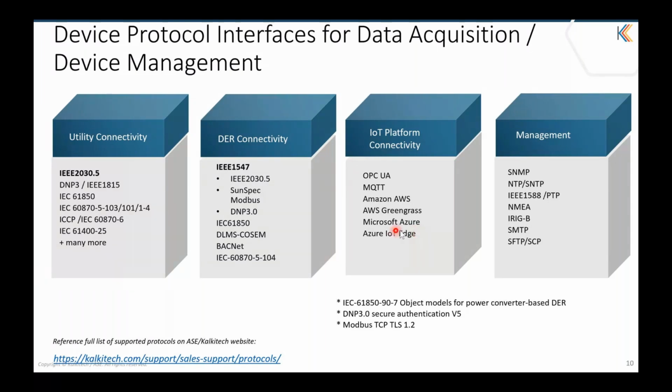And there are specific connectors to Azure Service Bus, Event Hub or IoT Hub. So there are different options which are already predefined and made available in the data hub, which enable users to expose data to a third-party system, and it also supports other standard protocols like OPC UA and MQTT if we want other standards-based protocol integration.